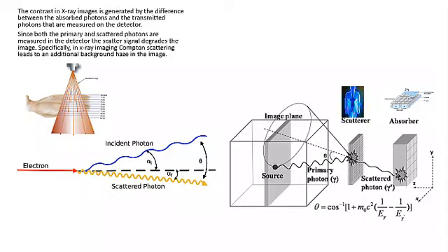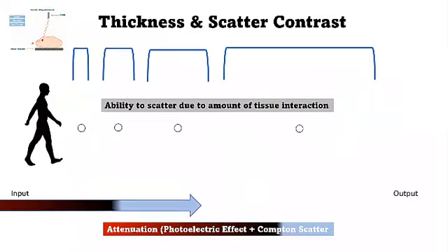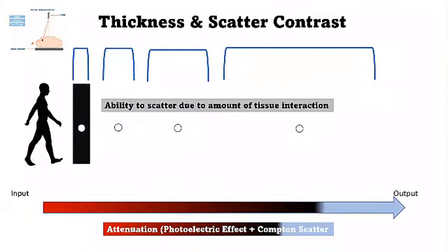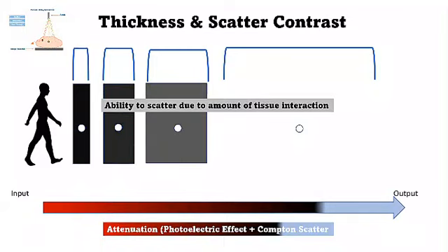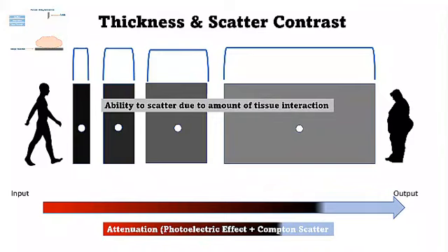Image contrast is generated by the difference between the absorbed photons and the transmitted photons that are measured on the detector. If the area acquired comes from a thinner or smaller patient as opposed to a larger or thicker patient, we'll get less scatter radiation. If the patient is larger or obese, we'll get more scatter radiation, which we do not want because it puts sort of a fog over the entire contrast of the image. Scatter radiation reduces contrast. So let's take a look at the attenuation of the beam and how thickness influences the contrast because of scatter radiation.